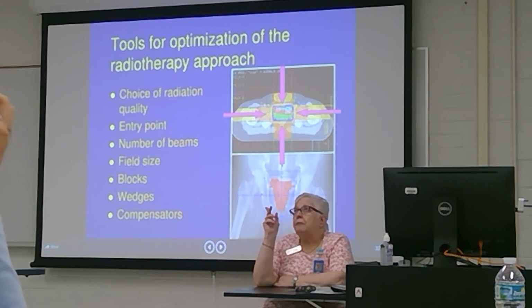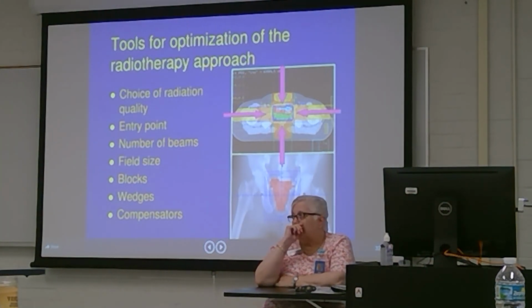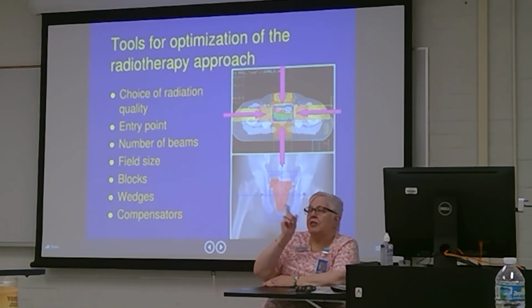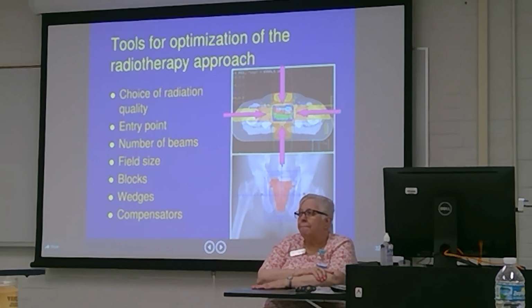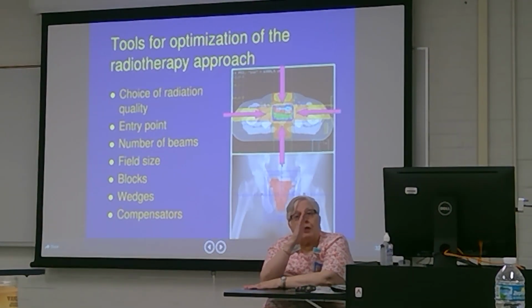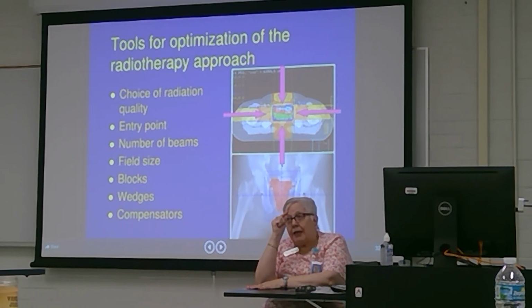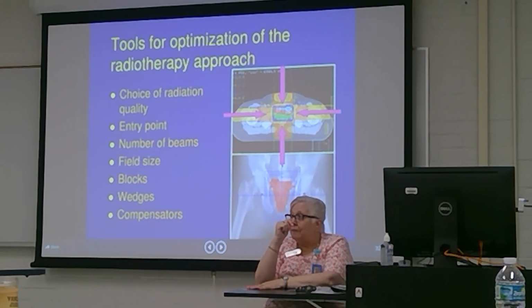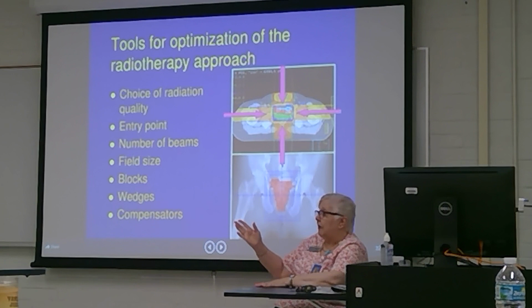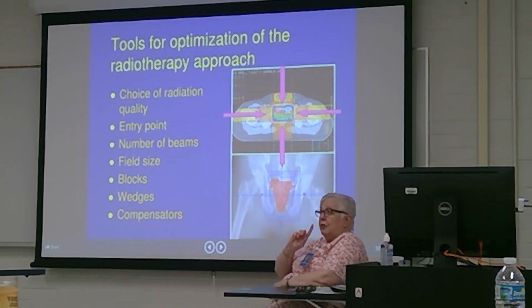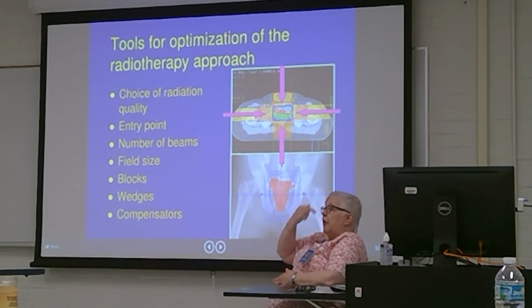What other laser do you have? Pardon? Transverse, where does that come from? Axial. Split the body this way. But I'm saying, where does the laser come from? The roof. So you'd have to move the gantry out of the way, right, to get your cross. Oh, I see what your question is now. I thought that was the AP laser. That is the AP laser. You were talking about the sagittal laser, which only goes one way.